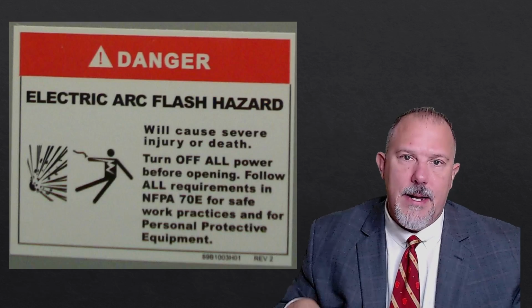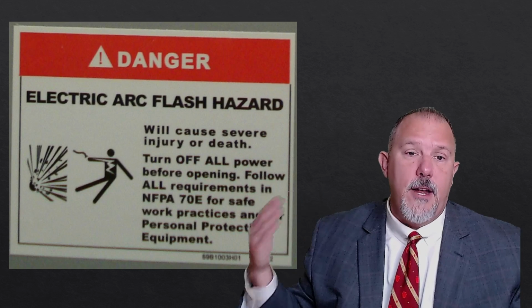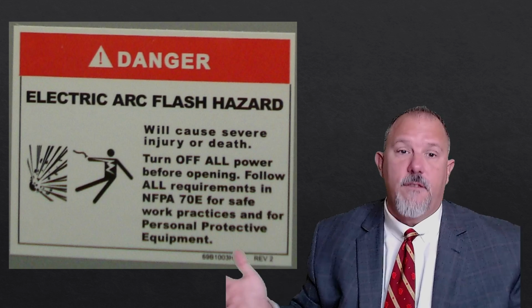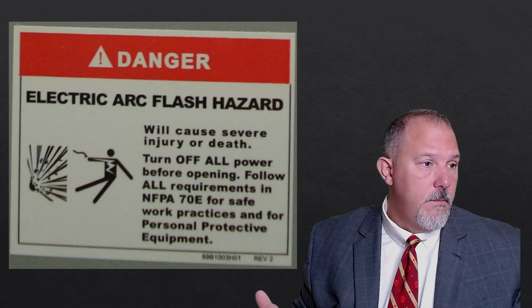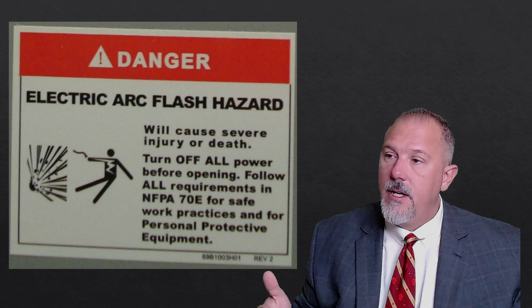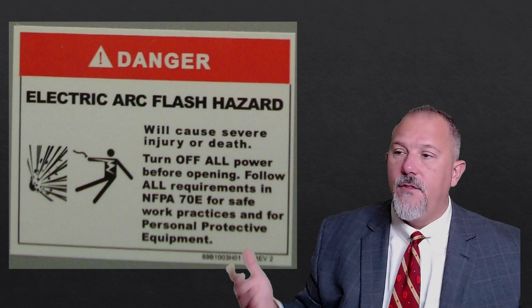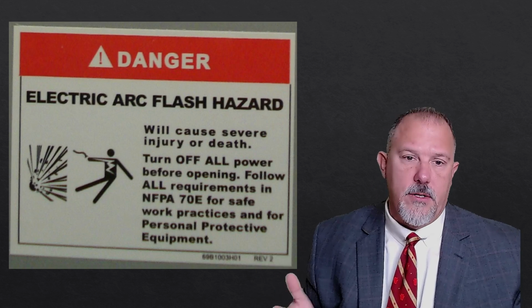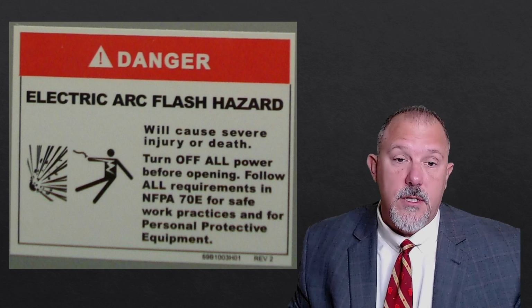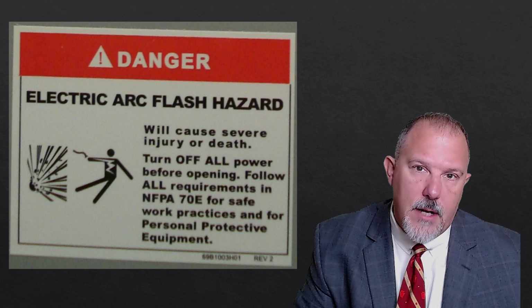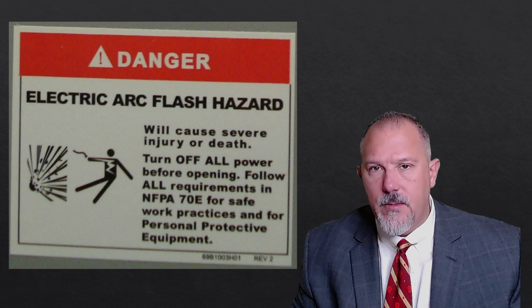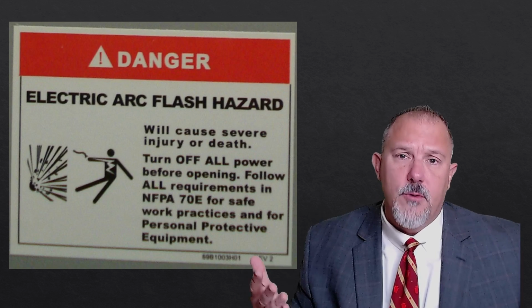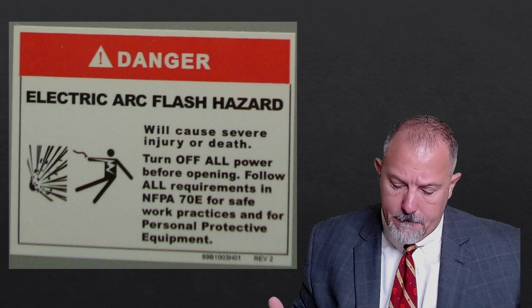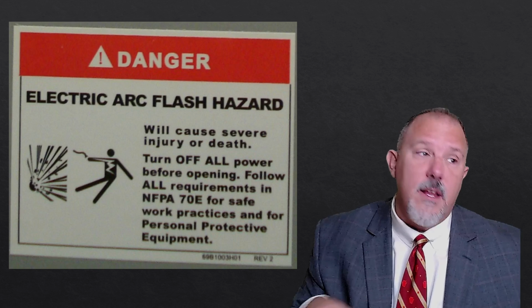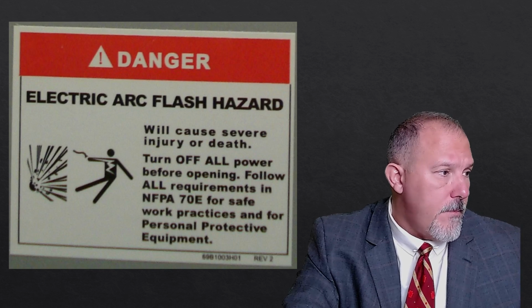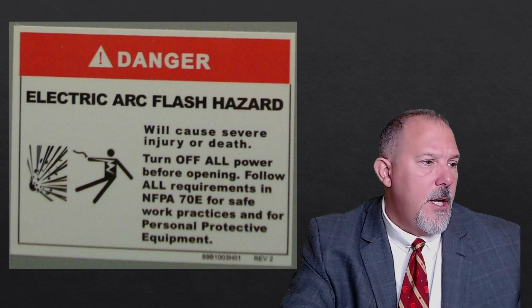It wanted those types of labels. But what we ended up with when it first went in the code was just a generic label like this that says, here's what the arc flash hazard is, which is just it'll cause severe injury or death, turn off all power before opening, and so on. It's just, hey, this is dangerous. And it went from you had to field label it to it could be shipped from the factory. In many of these cases, we put these labels on before it leaves the factory anyway. So 110.16 has developed and changed over time. And now it requires a little bit of both.